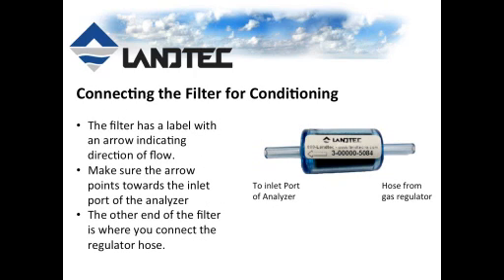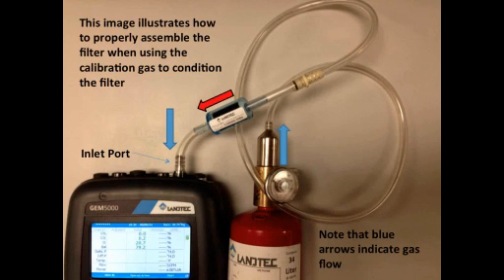A quick note on connecting the filter for conditioning. You'll notice that the filter itself has a direction arrow, and that arrow indicates the direction of the actual gas flow. You want to make sure that the arrow points towards the inlet port of the analyzer. In this image, the left side of the filter will be connected to the analyzer and the right side will be connected to the hose from the regulator of the high-purity gas bottle.